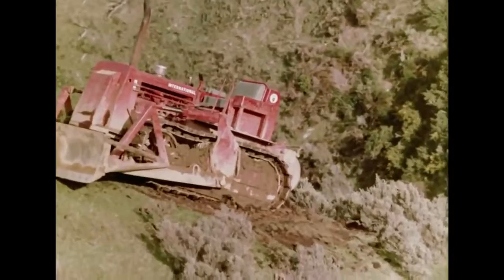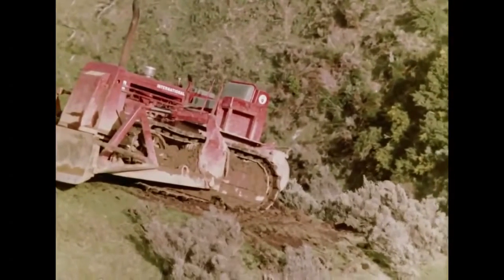First step in the tension stringing of overhead conductors is the pulling out of a steel wire haulage rope. This is usually done by tractor, but on very steep country, the wire rope from the tractor must be taken across gullies by hand.